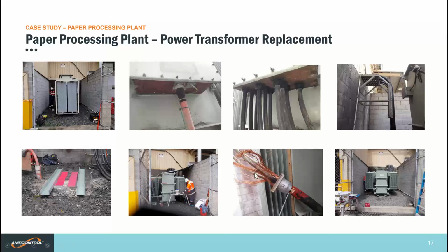Second last photo there being the XLPE cable. So there were modifications required to get the lead cone off it. That actually reused the lead wipe cone on there. So that termination was modified so that it could suit the new cable bushings. Last photo there on the right is the new transformer installed and ready for service.